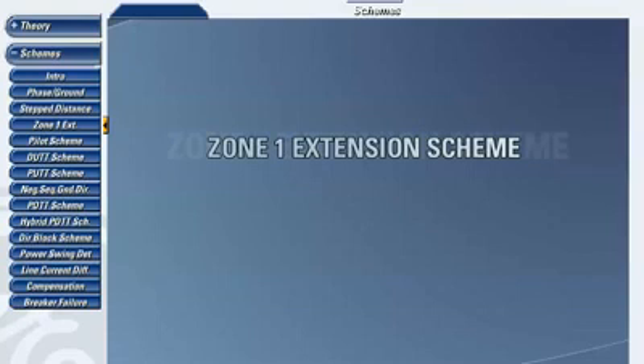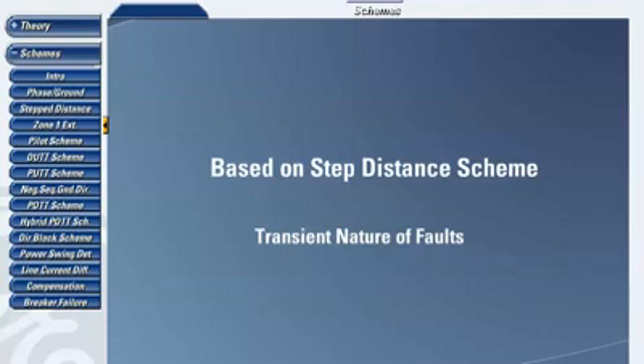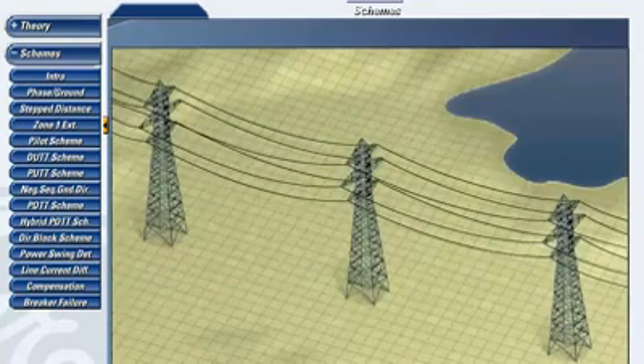Another type of non-pilot-aided scheme we will discuss is the Zone 1 extension scheme. The Zone 1 extension scheme is an enhancement to the stepped distance scheme covered in the previous section. This protection scheme operates on the principle that most transmission line faults are transient in nature, which means the fault is not permanent. For example, the most common cause of faults on transmission lines is lightning.